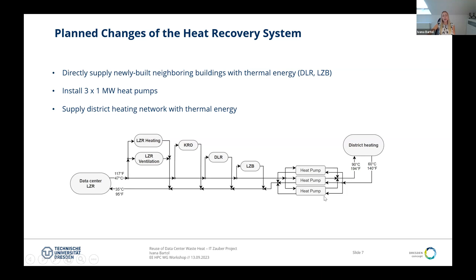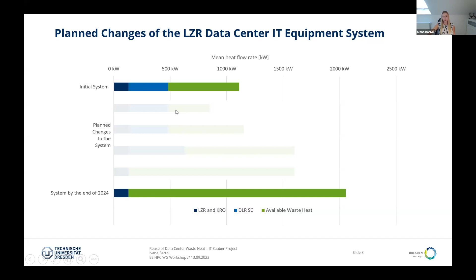Other than changes to the heat recovery system, some changes to the IT equipment system are being planned as well. From our initial system, there was around 1,100 kilowatts of potential waste heat. And by the end of 2024, there will be more than 2,000 kilowatts of potential waste heat. That is a direct result of adding new high-performance computers to our system, and also of connecting every part of the cooling infrastructure to the heat recovery system. For example, this side cooler.